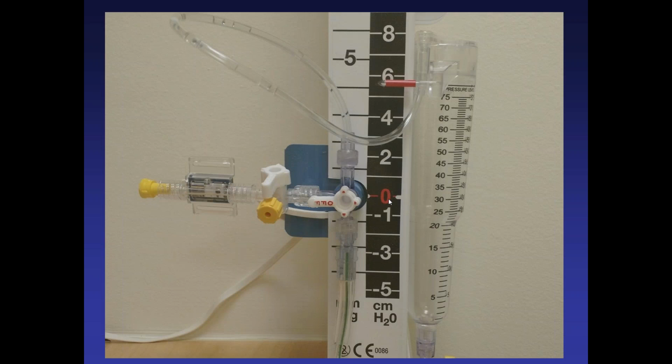And again, this 0 should be leveled with the external auditory meatus, or the tragus, which is what you'll read when you read about this normally. And it shouldn't be done by eyeballing it. There's a laser, like a laser pointer, that can attach to this exact point that they market. We don't use that here for some reason. The kit comes with this string with a bubble level on the middle of the string, and it just gets thrown in the garbage here for some reason. I don't know why. The nurses here prefer to use a long ruler with a level in the middle of it. But from my experience, mostly they're eyeballing it, and typically not adjusting it once they adjust the patient's position. So when you get called to see the patient with high ICP, just make sure you check the leveling of this.